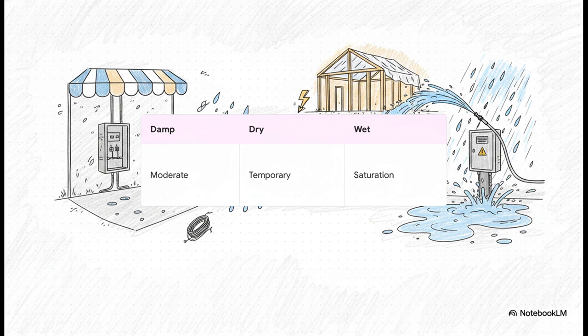Finally, we arrive at Section 5, Everyday Environments, where code meets reality. Now, what's really interesting about this matrix is how the code breaks down environmental moisture levels side by side. It doesn't leave room for guessing, it strictly classifies. A damp location is an area that sees moderate moisture, like under an exterior canopy. A dry location? That might get temporarily wet, like an unfinished building still under construction, but normally it's perfectly dry. And then you have a wet location, which is subject to actual liquid saturation. Think vehicle washing bays or completely unprotected outdoor spaces. These aren't just labels. These strict definitions tell you exactly what kind of wire and enclosures you are legally allowed to use in those spots.